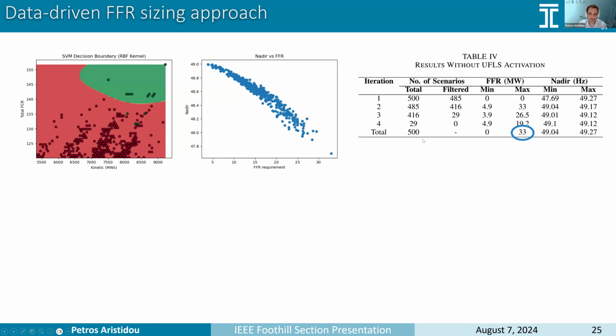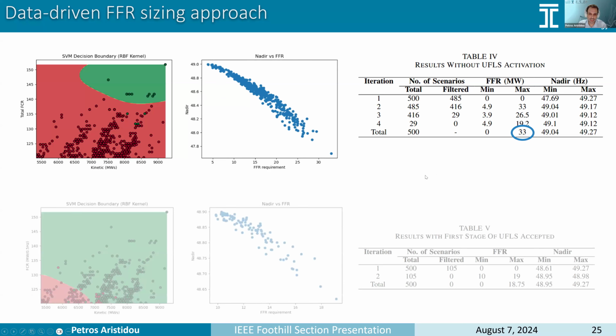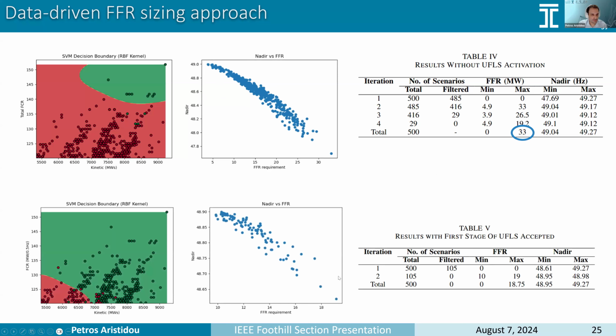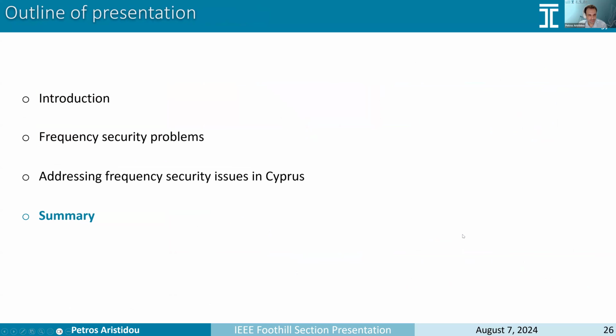This is without under frequency load shedding activation. And if we consider a first stage under frequency load shedding is accepted, so we accept that we can activate the first stage, that is 4% of the consumers disconnected, then running the same analysis ends up that we only need around 19 megawatt of fast frequency reserves.